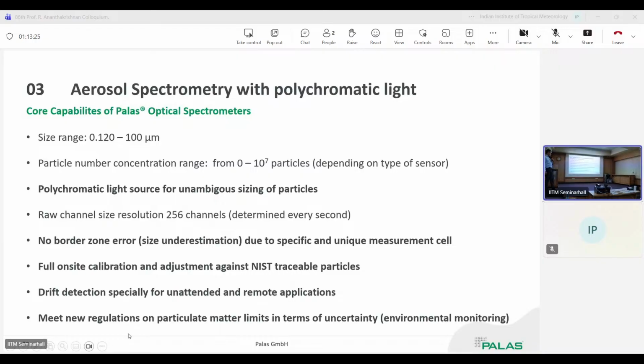Also a very important topic for environmental measurement, but also for all our devices which are used for spectrometry. Drift detection is also something very important for environmental measurement. So if you see channel drifts of the system, due to optics or LEDs which degenerate, or optics which are spoiled, you have less reflection and the particle size seems to be smaller. And this we can see with our system if something is happening in that area. And of course, we need to meet new regulations on particulate matter limits. In terms of uncertainty, this is a topic we can talk about at the beginning. And here I will show what is behind the topic.